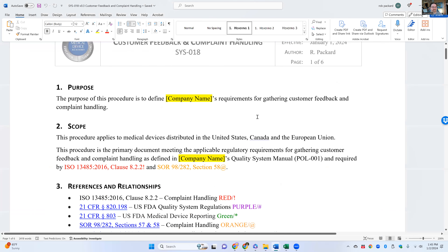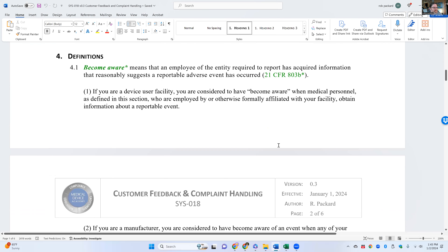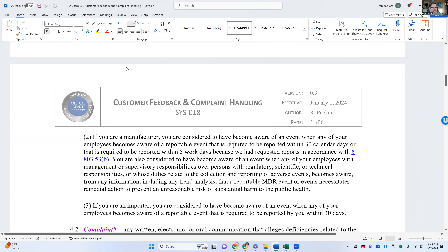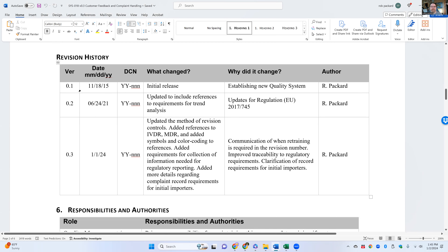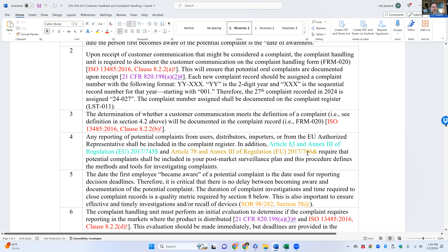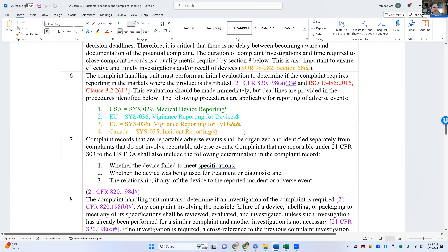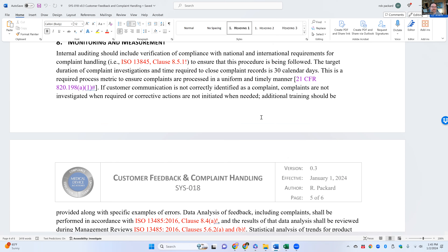Our complaint handling procedure is now a six-page procedure, not a four-page procedure anymore. Here's our flowchart showing the inputs and outputs of the process. We have definitions with cross-links to the regulation. Here's the revision history — you'll change this to 1.0 when you approve your procedure. We give the roles and responsibilities; you would change those to the titles in your company. Throughout the procedure, we have hyperlinks to every single requirement with symbols and color coding, so you can find exactly what you're looking for whenever an auditor is asking. At the bottom of the procedure, we also include what kind of metrics we recommend for a complaint handling process. One minimum requirement is tracking how long it takes to close complaints — typically the target is 30 calendar days, because you need to make your regulatory reporting decisions in that timeframe as well.